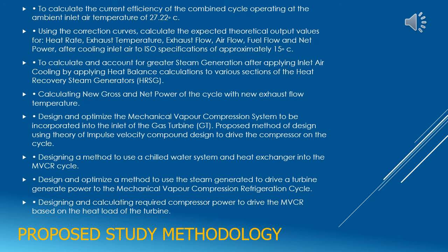To design and optimize the mechanical vapor compression system to be incorporated into the inlet of the gas turbine. Along with the MVCR cycle, a method needs to be designed to use a chilled water system and a heat exchanger in the MVCR cycle. Design and optimize a method to use the steam generated to drive a turbine to generate power for the mechanical vapor compression refrigeration cycle. Hence, in doing so, the design and calculations need to be done to find out the required compressor power to drive the MVCR cycle based on the heat load of the turbine.